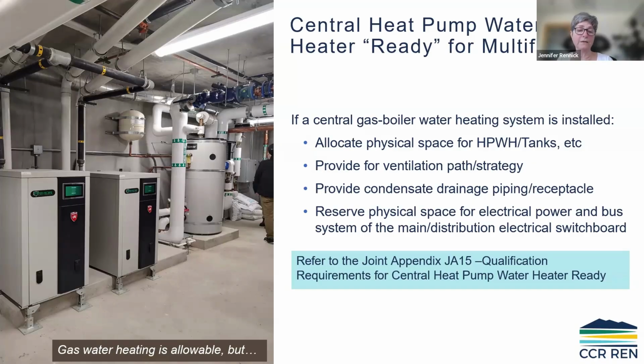So gas water heating is allowed again, but you have to allocate the space for the heat pump water heaters, or for the compressor and the tanks. You have to really spell out what the ventilation path and strategy is going to be. You have to provide your condensate drainage, et cetera, and make sure all the electrical is met. And then these requirements are going to be found in the joint appendices, JA15.